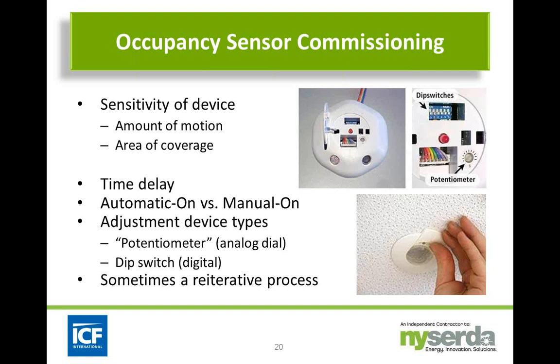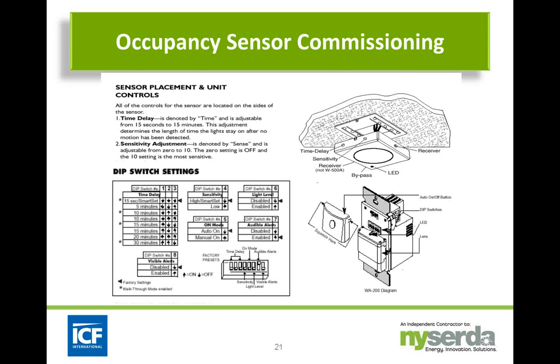Dip switches let you turn one switch on, one off, in various sequences to create different adjustments in the device. Sometimes you'll be doing this repeatedly as you go through the process, so check your instructions. It may help during commissioning, or even when writing your specification, to consider how complicated the commissioning process is for a particular device. The graph on slide 21 shows the dip switch configurations—on and off combinations—that determine how many minutes or seconds the device takes to turn off.